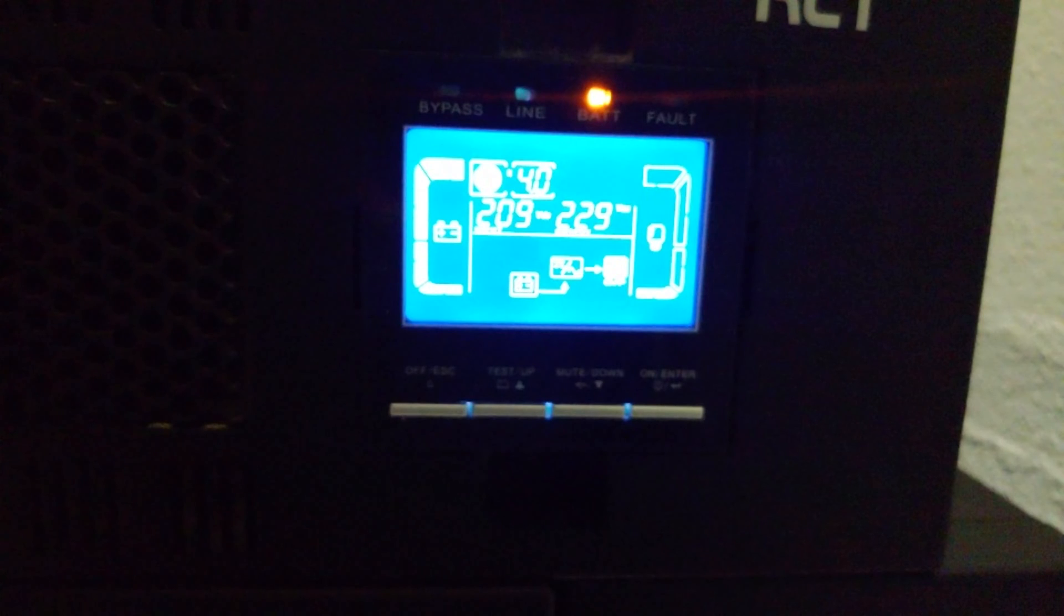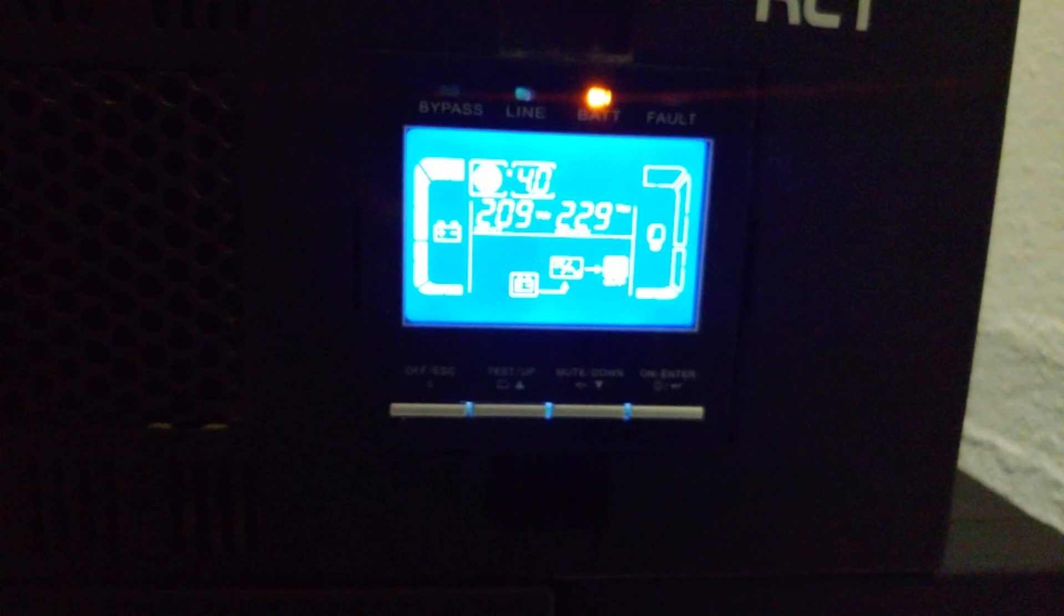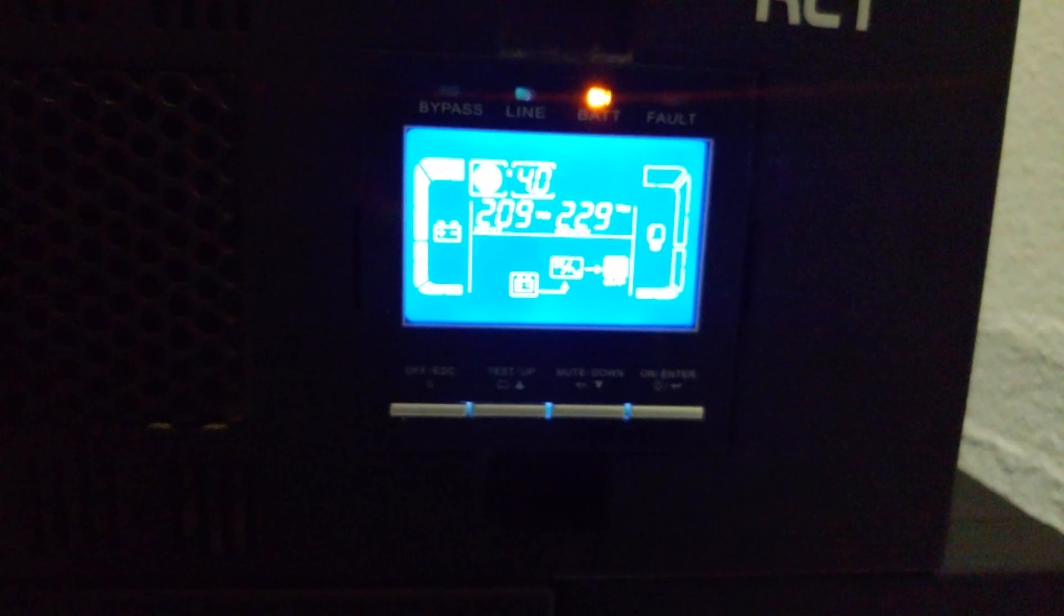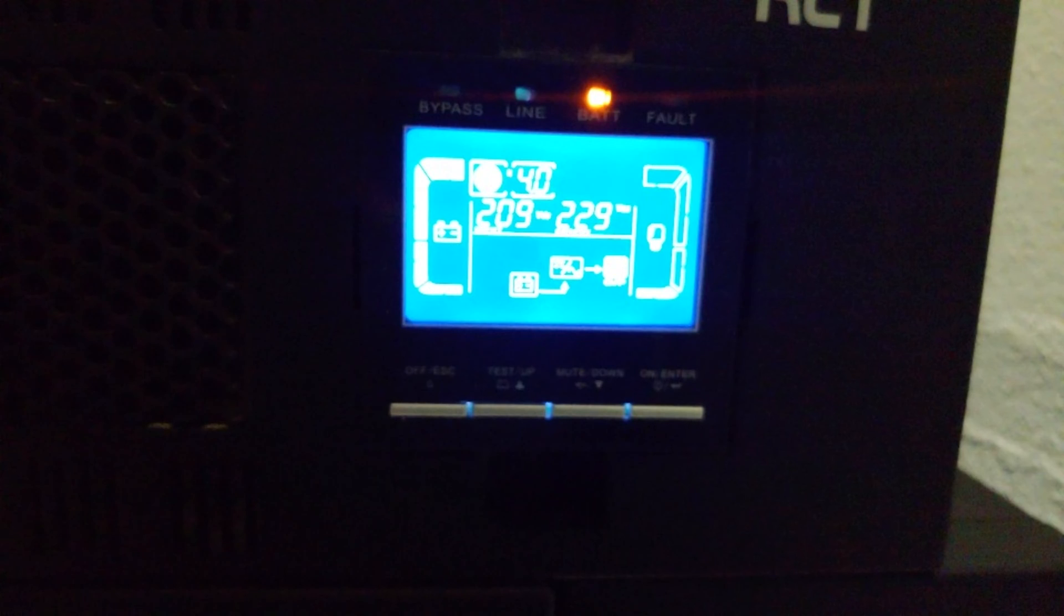Okay, just explaining how the backup time is calculated. There it says it's got four hours left, and then it dropped to 2.3. What it does is it looks at the loading and it compares that to the battery banks that are available. So if you have four battery banks and you tell the UPS that there's only two battery banks, then what will happen is the UPS will cut out earlier even though the battery banks are available. So it actually is not using a measured value—it's using a calculated value. So it's very important to tell the UPS that you've added battery banks, otherwise it won't stay on for the time that you want it.